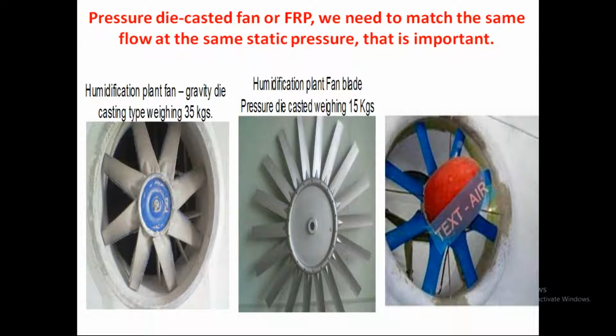In some textile mills where the plenum size is less, they can go for an aerofoil type FRP blade, where it is not a hollow FRP, it is a thick FRP. Normally, it is glass reinforced FRP. The glass reinforcement will definitely increase the weight of the fan, but the aerofoil profile of the fan will achieve excellent savings, almost 15 to 20% is achievable.